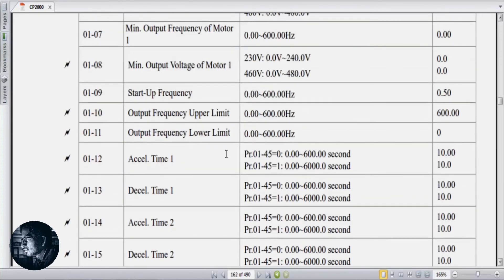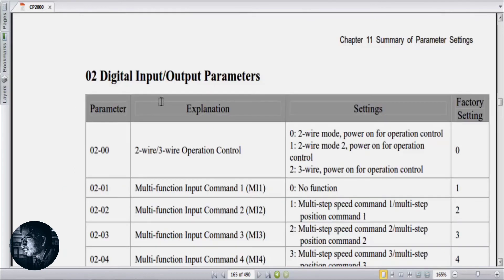Then parameter 01-12, which is acceleration time, and parameter 01-13, which is deceleration time. Both of these parameters are to be set as per customer requirement or application. Then parameter 02-00, operation mode — we set this to 2 for 3-wire control.